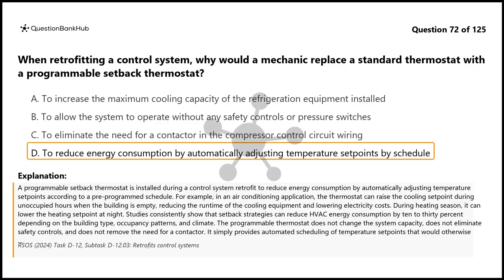During heating season, it can lower the heating setpoint at night. Studies consistently show that setback strategies can reduce HVAC energy consumption by 10 to 30% depending on the building type, occupancy patterns, and climate. The programmable thermostat does not change the system capacity, does not eliminate safety controls, and does not remove the need for a contactor. It simply provides automated scheduling of temperature setpoints that would otherwise require manual adjustment by the building occupant or operator.